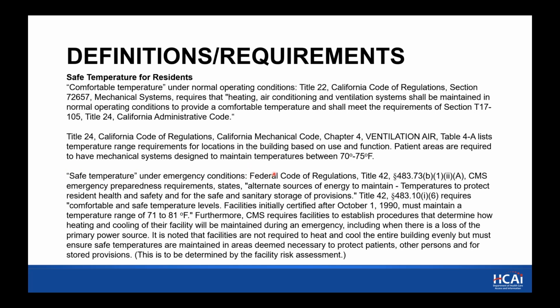And that is coming from the federal requirements of the Code of Federal Regulations. The CMS emergency preparedness requirement states that alternate sources of energy are needed to maintain temperatures to protect resident health and safety and for the safe and sanitary storage of provisions. That temperature is identified as 71 to 81 degrees Fahrenheit. We are not making up the number when we come to this. We didn't just pull it out of the air. We are actually using federal guidance on defining what a safe temperature is.